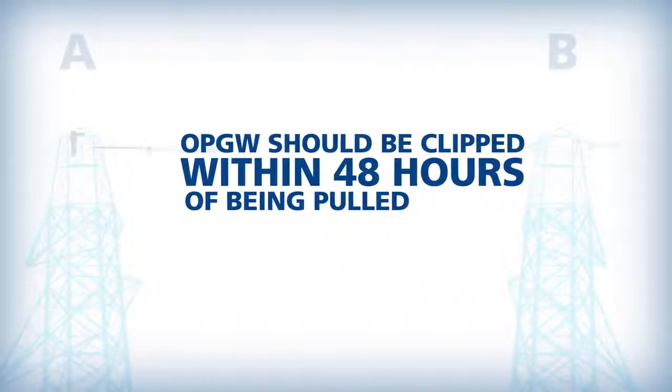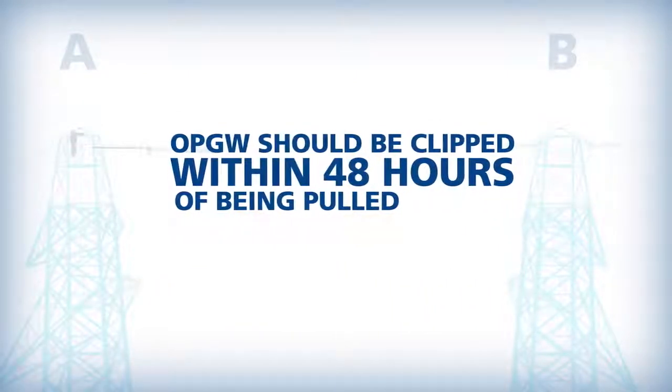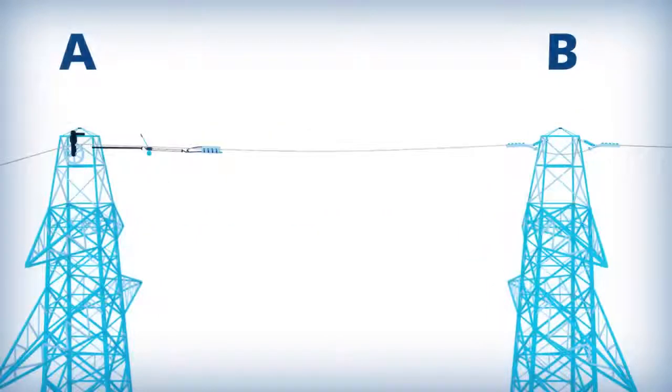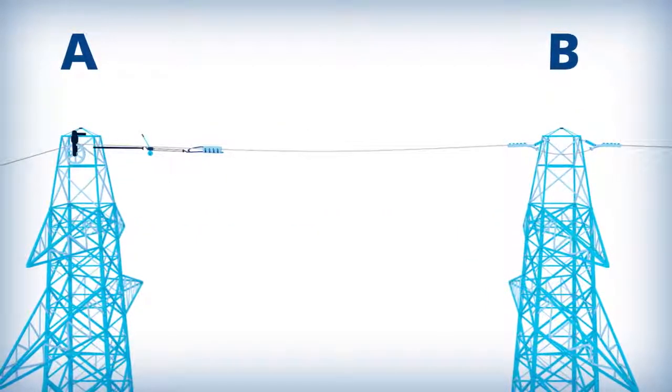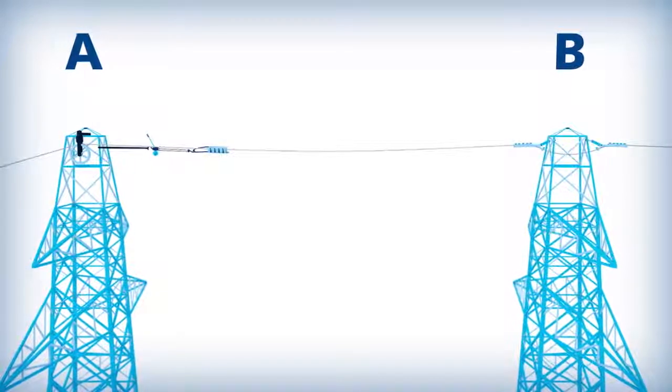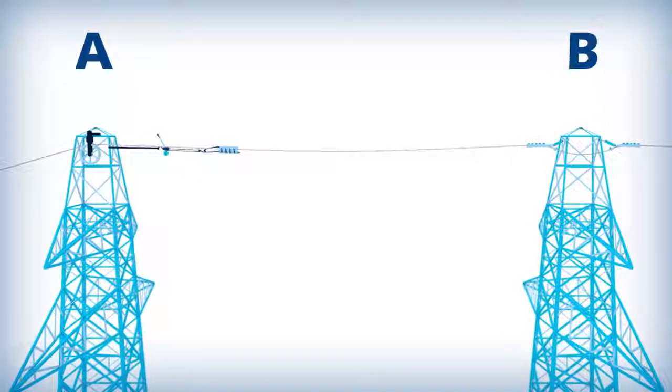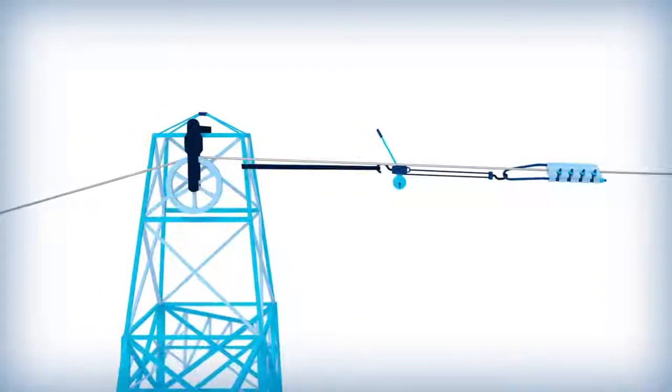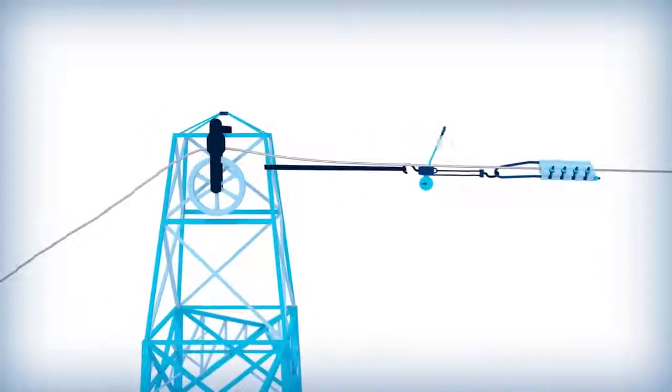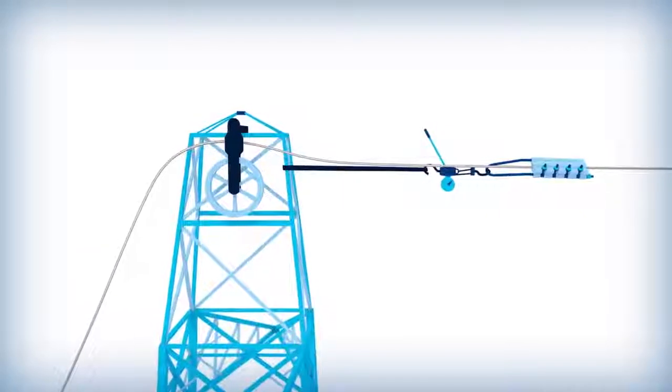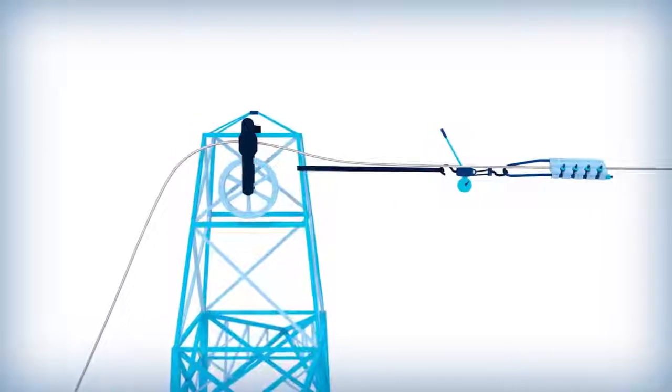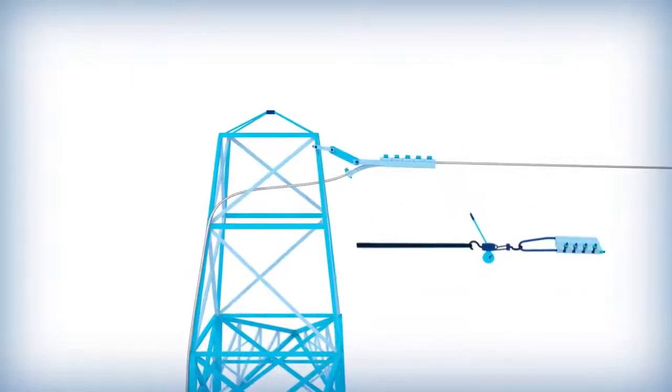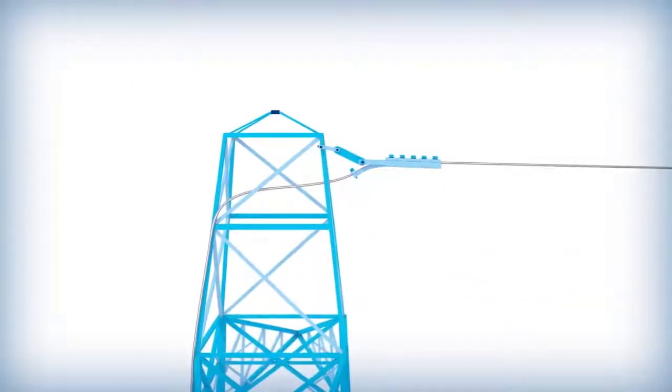OPGW should be clipped into dead ends and suspensions within 48 hours of being pulled. To lift the OPGW from the stringing block, attach come-alongs to the cable on each side of the structure and place a hoist on the structure arm. The hooks of the hoist are placed on the come-along and jacked up to pull the OPGW out of the stringing block. The stringing block can then be removed and a dead end can be placed to attach the OPGW to the structure.